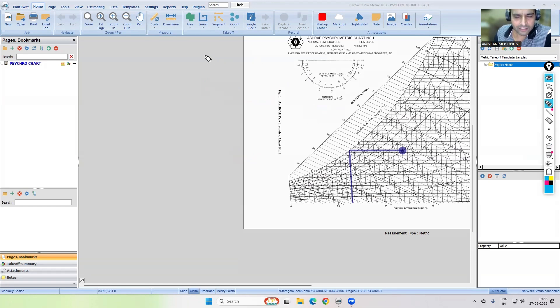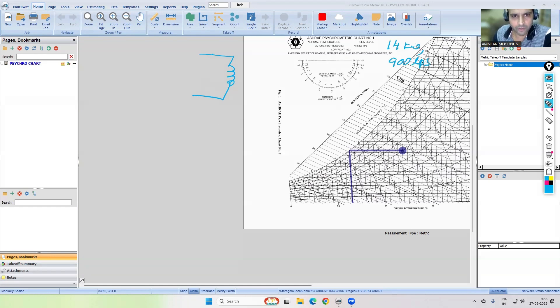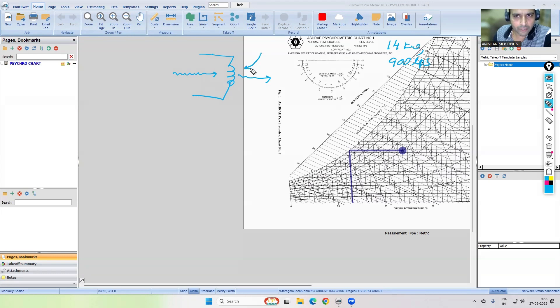For example, I have a cooling coil and a space. I did the heating and cooling load calculation within the space and got nearly 14 kilowatts of total coil load, with nearly 900 liters per second of air flow rate. The return air of 900 liters per second from the room will be circulated through the cooling coil, and this coil will be able to extract 14 kilowatts of total heat from the space.